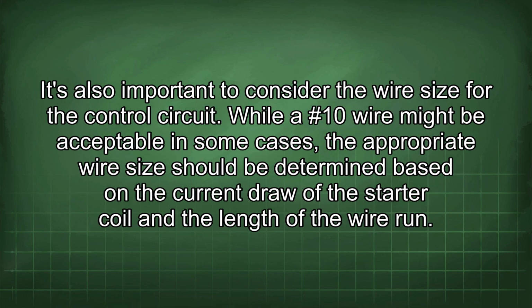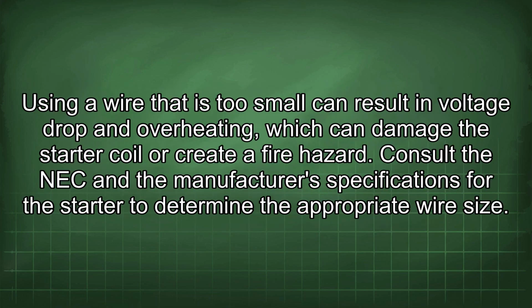safely. It's also important to consider the wire size for the control circuit. While a #10 wire might be acceptable in some cases, the appropriate wire size should be determined based on the current draw of the starter coil and the length of the wire run. Using a wire that is too small can result in voltage drop and overheating, which can damage the starter coil or create a fire hazard. Consult the NEC and the manufacturer's specifications for the starter to determine the appropriate wire size.